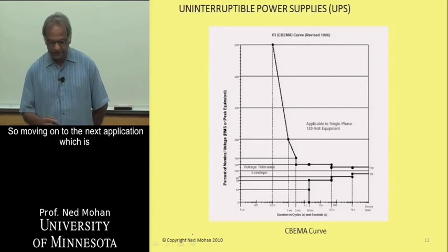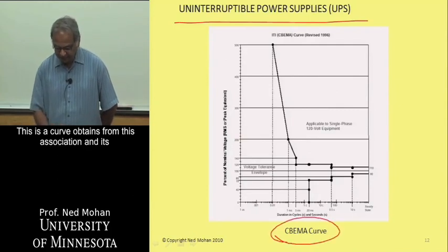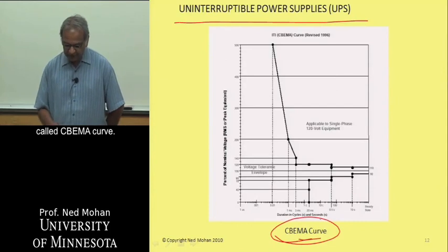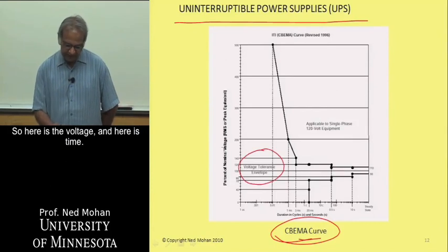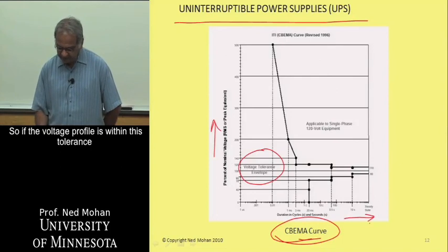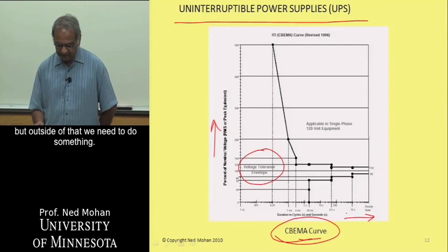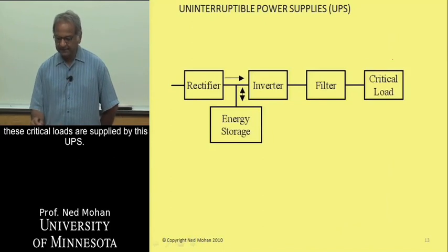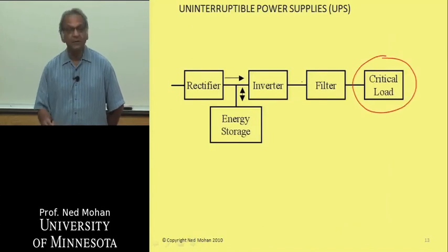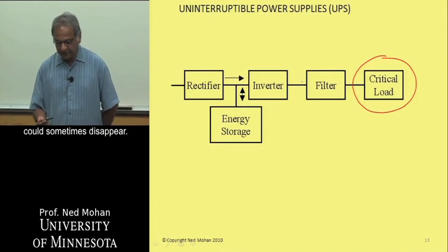So moving on to the next application, which is so-called UPS, uninterruptible power supplies. This is a curve obtained from this association and it's called CBEMA curve. It shows this voltage tolerance level. So here's the voltage and here's time. So if the voltage profile is within this tolerance envelope, then there's no problem. But outside of that, we need to do something. So for critical loads, what is commonly done is that these critical loads are supplied through this UPS, not directly from the utility supply because that could sometimes disappear.